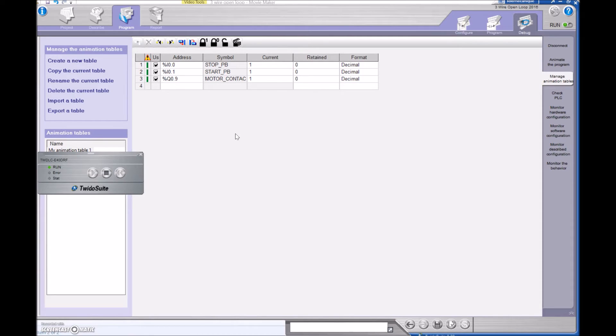I'm now going to let go of the start push button — it'll go to a zero, but the motor contactor will be maintained at a one. So as I press that start push button I'm using an Examine If Closed — examining if there's voltage. Right now there's no voltage to that input terminal; if I press that button, voltage is applied to that input terminal and it changes the data table from a zero to a one. There are only two states: zero is off or no voltage, and one is on or voltage applied.